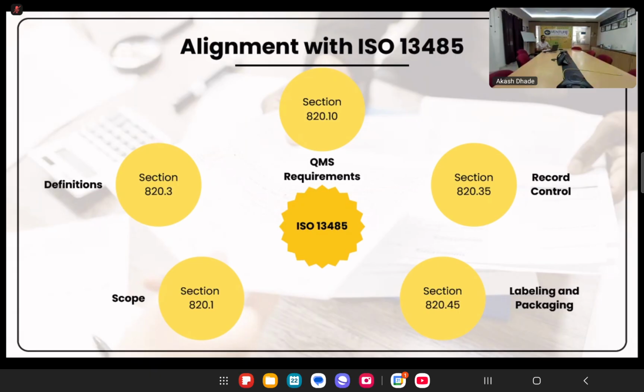Okay, so UDI also asks the manufacturer to keep batch records for all the batches that are produced in their manufacturing facility. So if you have an SOP for UDI, your SOP for UDI should take care of all these aspects. For example, the UDI SOP will tell you what to do if you have different configurations of your device. For example, if your device can go into a system as well as go as a single device, those two different configurations should have different UDIs so that it is traceable throughout its life cycle. So your UDI SOP will specify that my configuration A will have one UDI and my configuration B will have a different UDI, and it will also have different batch records, and based on that the UDI will be placed on the final packaging or the labels. Okay, so that is the example of a UDI SOP, which is in alignment with ISO 13485 as well as QMSR.